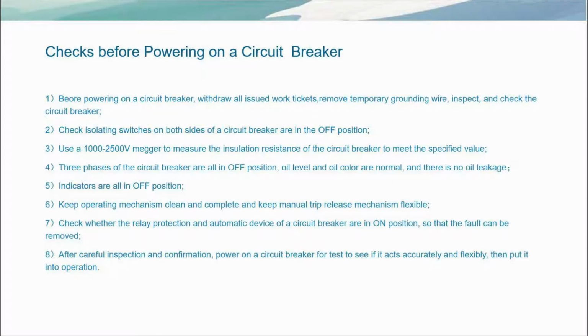1. Before powering on a circuit breaker, withdraw all issued work tickets, remove temporary grounding wire, inspect, and check the circuit breaker. 2. Check isolating switches on both sides of a circuit breaker are in the off position. 3. Use a 1000 to 2500V megger to measure the insulation resistance of the circuit breaker to meet the specified value. 4. 3 phases of the circuit breaker are all in off position, oil level and oil color are normal, and there is no oil leakage. 5. Indicators are all in off position.